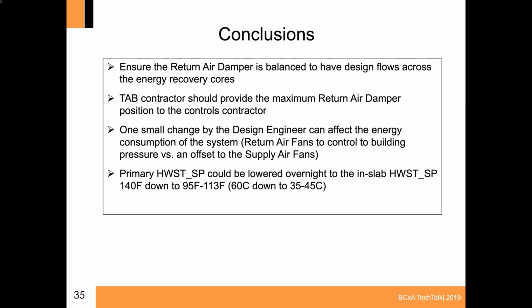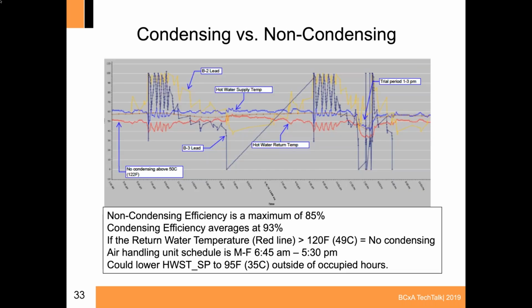So another thing that we noticed is, and I'm just going to go back to this slide right here. If you can make out from about 5 p.m. or 6 p.m. on until say 6 a.m. or 6:30 in the morning, you can see that the return temperature is well above that 50 Celsius for most of the time. When these air handling units are off outside of their schedule, the building is heated by radiant in-slab heating, and that set point is more in around a 45 degrees Celsius set point. So if you could have it controlled that your hot water supply temperature set point from your boiler gets decreased, then you're going to have even more significant savings almost every night as this is happening.